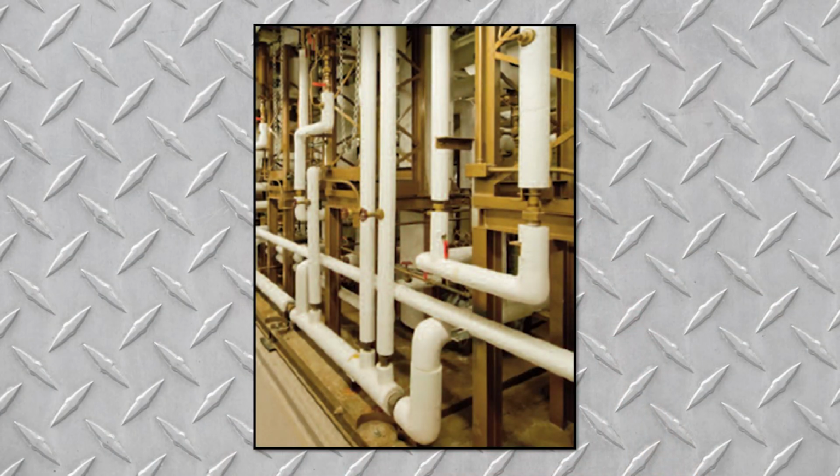Now, these steam distribution systems or steam pipes are hot, very hot. And therefore they require significant insulation for both safety reasons and for energy efficiency. This is why we spend a lot of our time looking at insulation during plant site visits. We're looking to see if it is complete, and we're looking to see if there's any damage to the insulation.